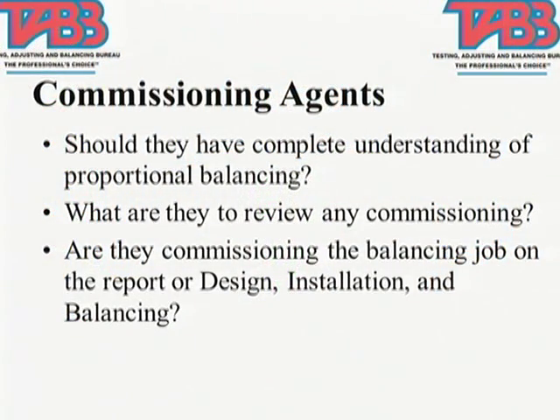It's imperative that the commissioning agent is an industry expert so that they can recognize what to do in those situations and say, you know what, we're in this big room. Yeah, we don't have the plus or minus in that one back grill. We're at 40% of flow, even if it's terrible. You know what, in that area we can increase the other ones 20%. So it's given more than design. So in that area or zone of the building, we're given the proper amount of air to meet design.